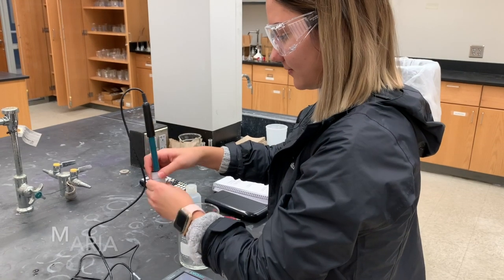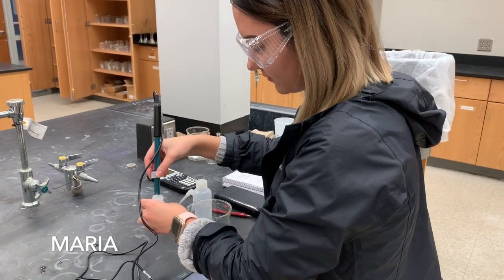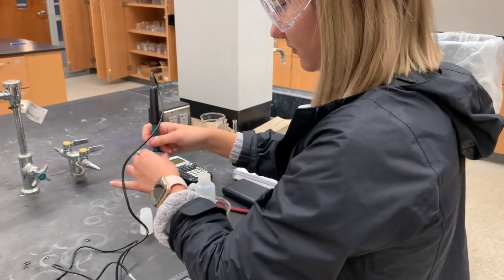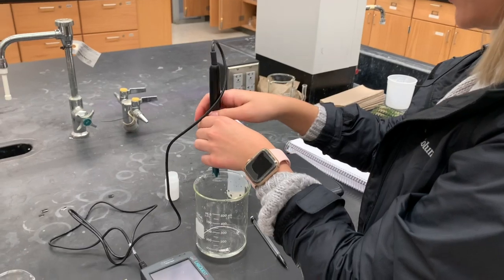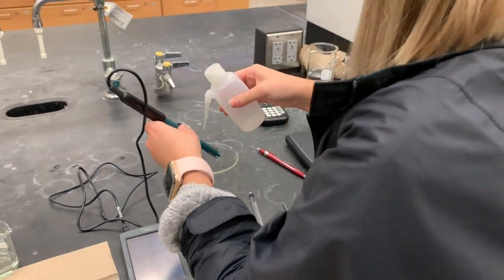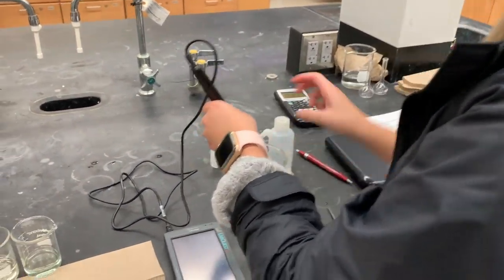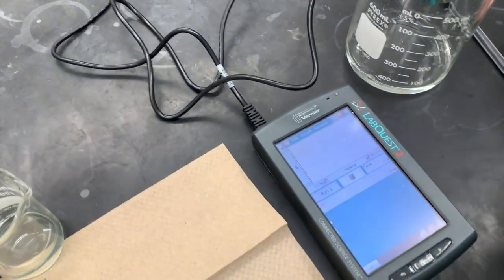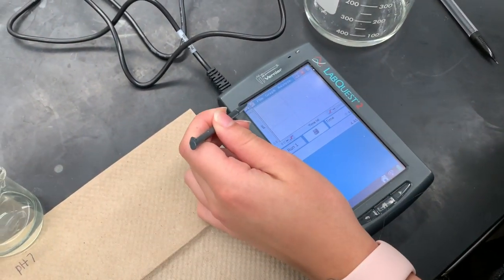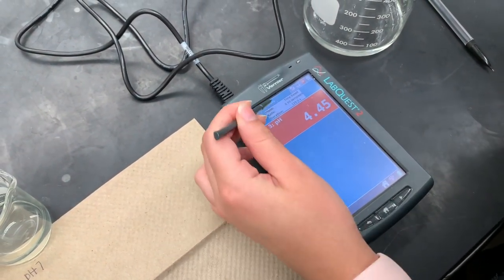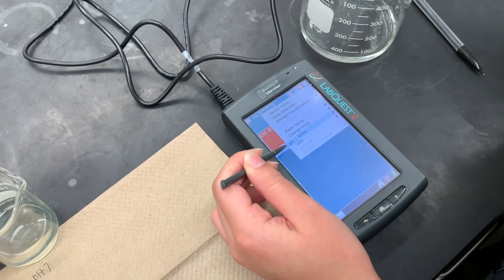At the beginning of the experiment, the pH meter must be calibrated. To do so, the probe must be taken out of its storage container and rinsed with distilled water. On the meter, you can find the Calibrate tab under the Sensors tab on the main menu. Now the probe can be placed carefully in a buffer solution of a known pH while you enter the numerical value of the pH on the meter.